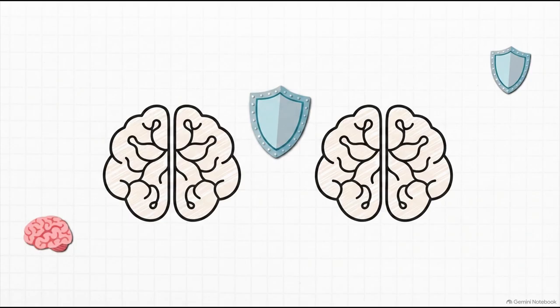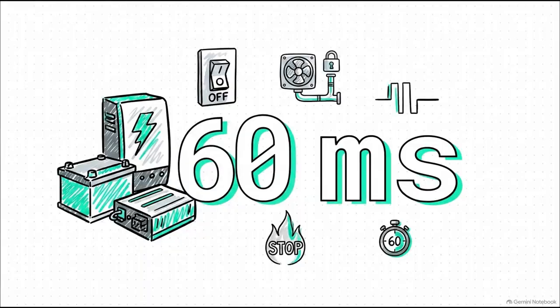If their results differ by more than 5 volts, the system assumes a software glitch, like a random single bit flip in the memory, has occurred. It forcefully shuts down the relay drives in under 100 microseconds. And all of this leads us to one absolutely vital number: 60 milliseconds. This is your fault-tolerant time interval, or FTTI.